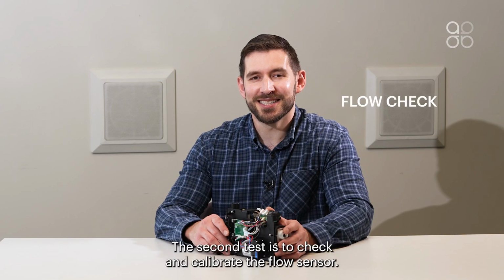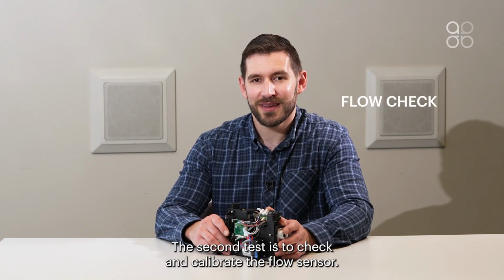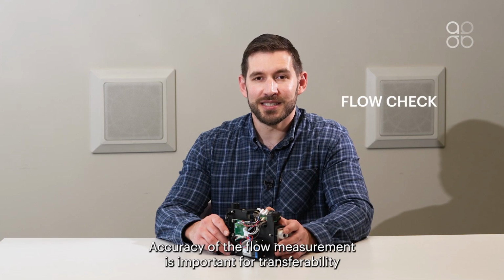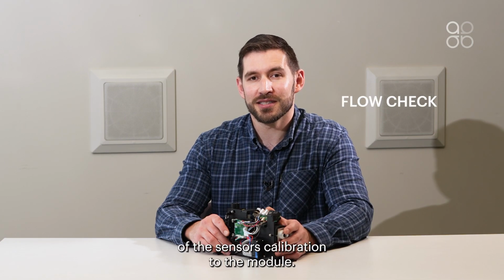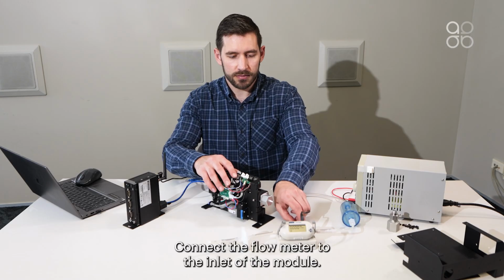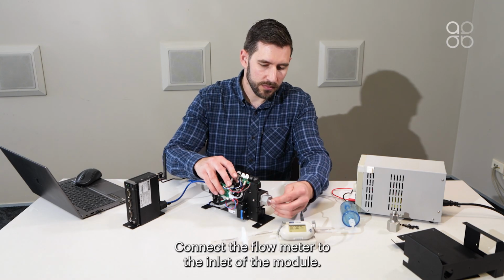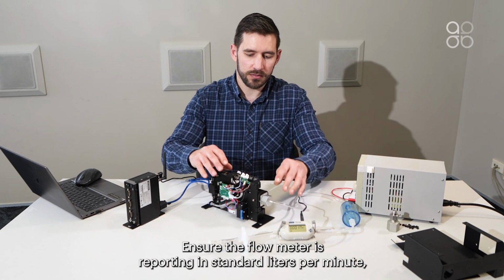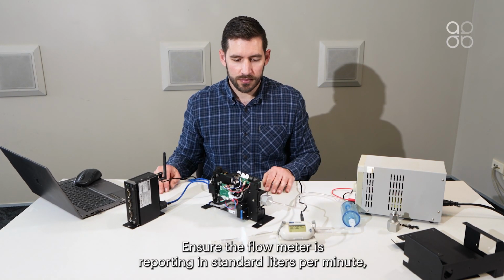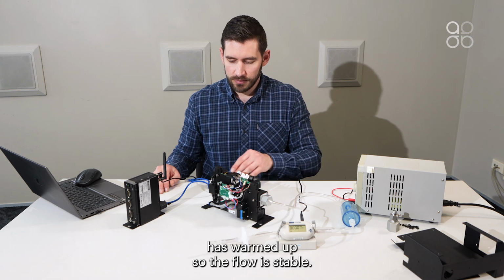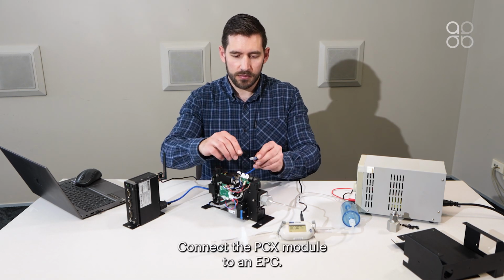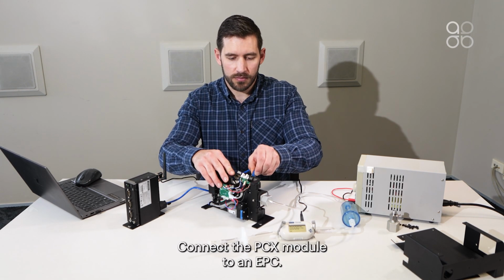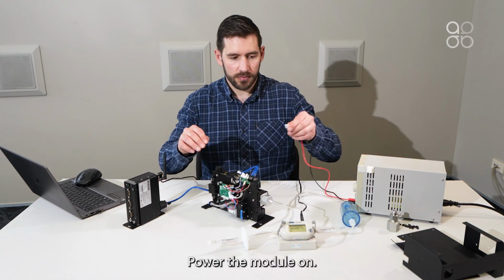The second test is to check and calibrate the flow sensor. Accuracy of the flow measurement is important for transferability of the sensor's calibration to the module. Connect the flow meter to the inlet of the module. Ensure the flow meter is reporting in standard liters per minute and has warmed up so the flow is stable. Connect the PCX module to an EPC. Power the module on.